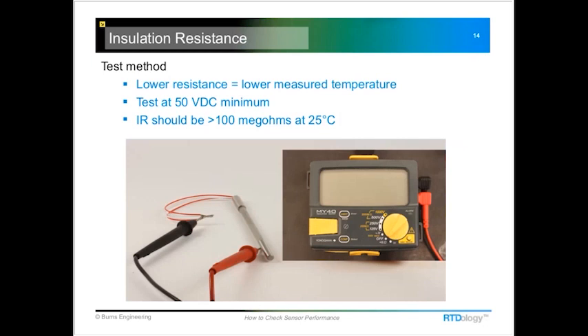The method that we use to test this is with a megohm meter, and we'll just bundle the lead wires and touch one of the leads to them, and then touch the other one to the probe sheath and note the reading on the meter. The test as a minimum should be done at 50 volts DC, and it should be greater than 100 megohms at room temperature. If you look at manufacturer specs, a lot of them are going to say they do the test at 500 volts and 500 megohms at room temperature. And for secondary temperature standards, it may be 1,000 megohms is what they're trying to shoot for.